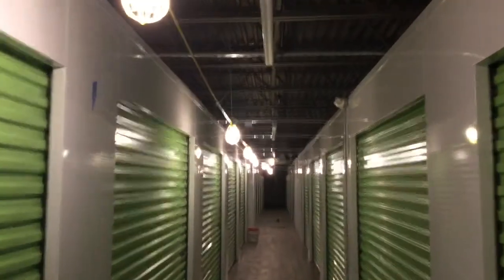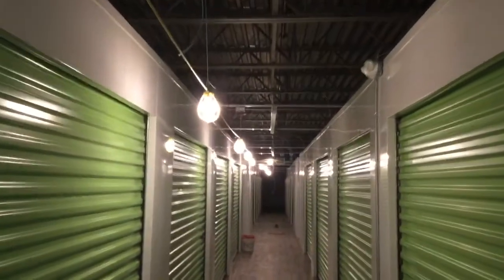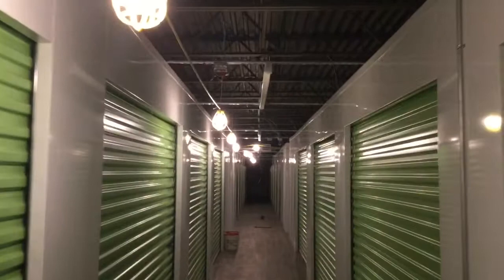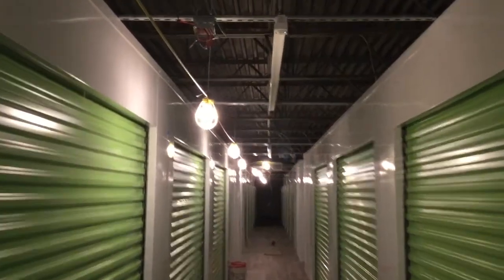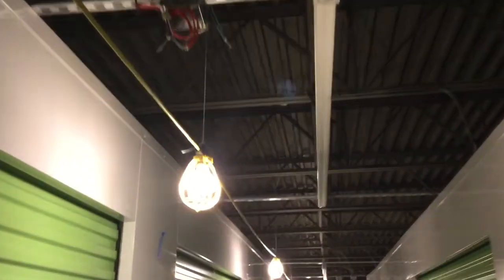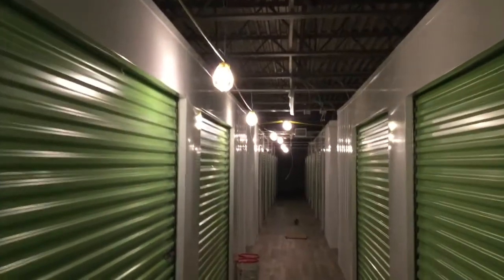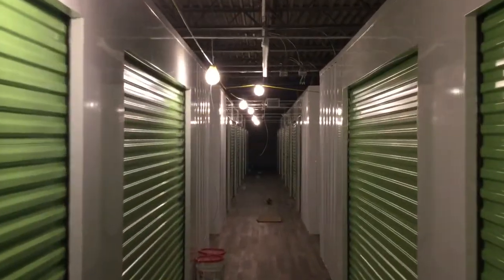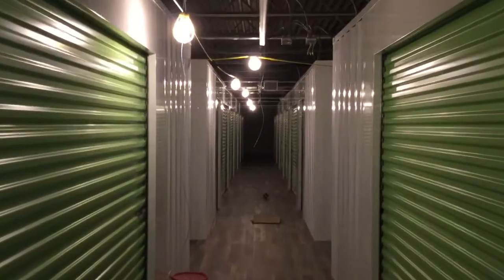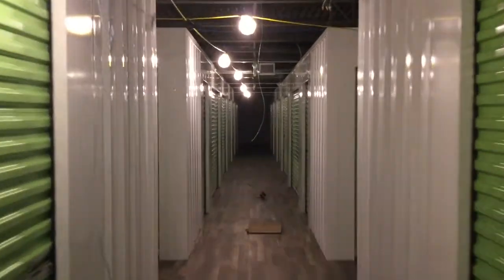Temp lights are still in, but as soon as the switchgear is in, we'll be able to turn over to permanent power, and all the fixtures have already been tested and do work. All the fire alarm wiring has been run, but still needs devices installed. As soon as the power is complete and we have boarded in the office area, we'll be putting the fire alarm panel in for testing.